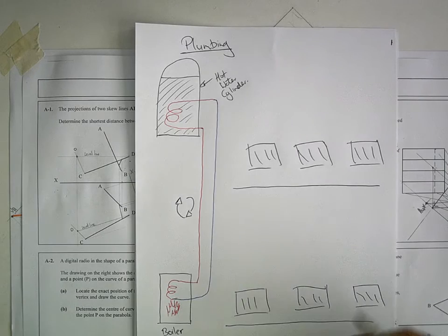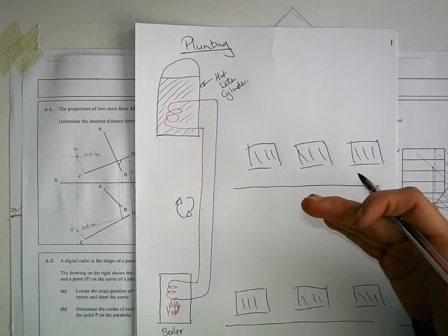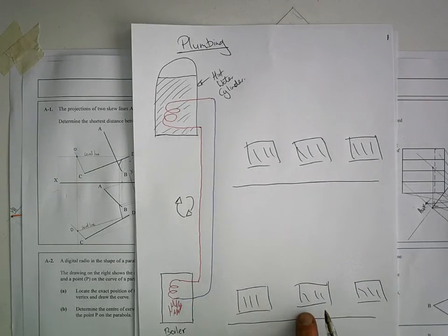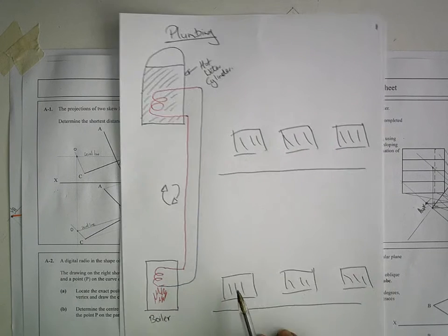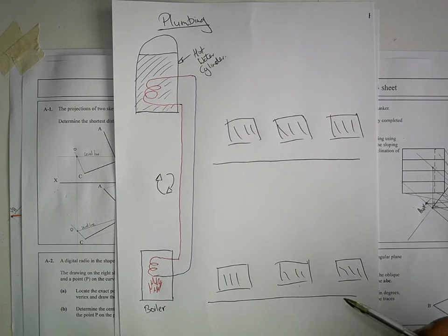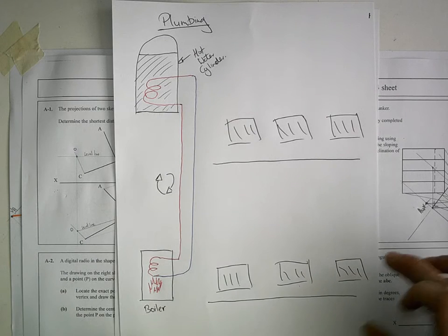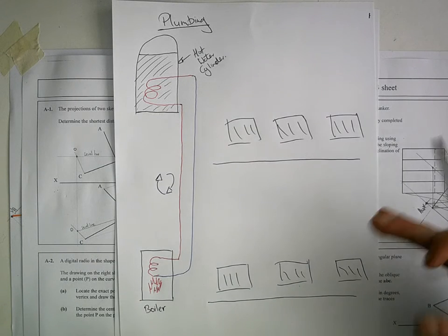And again, they're going to be piped up directly to the boiler, so they don't mix with other water. So from the boiler house, you're going to have a second system coming directly to your radiators. Now the old system was that it went from the first radiator and then to the second one and then to the third one and then the whole way back. But what happened was the third radiator would take ages to heat up. So what they now do is they join them up independently, so each radiator is getting the heat at the same time, and they'll all heat up universally.